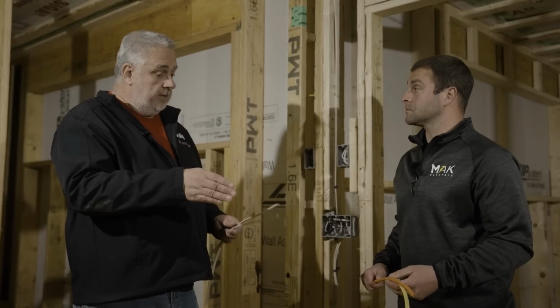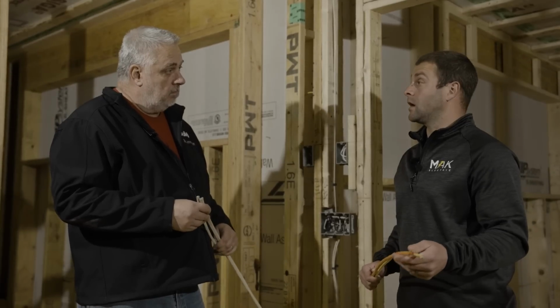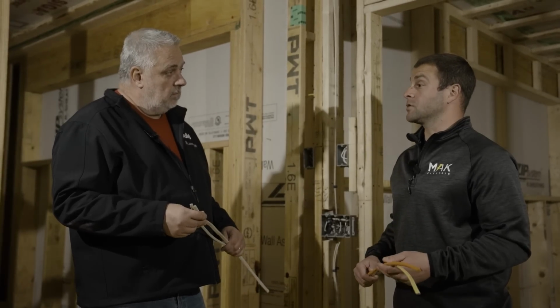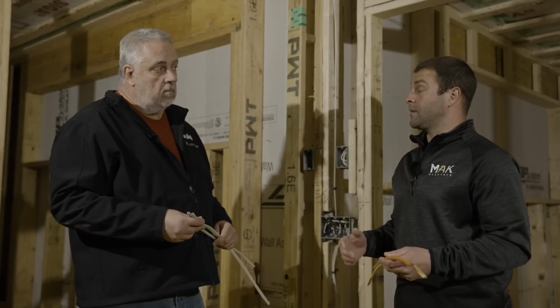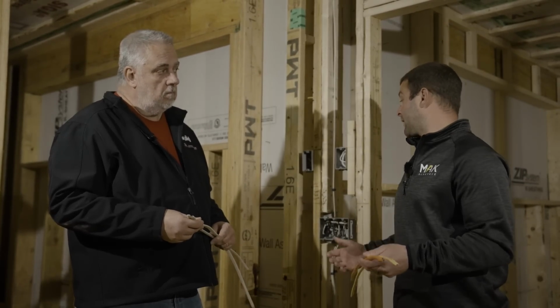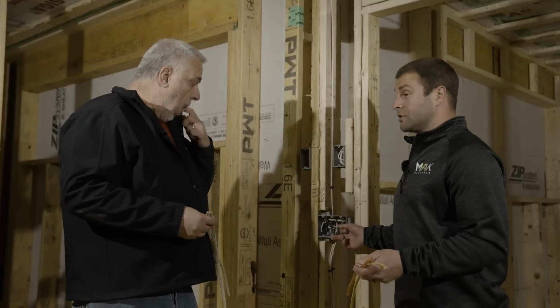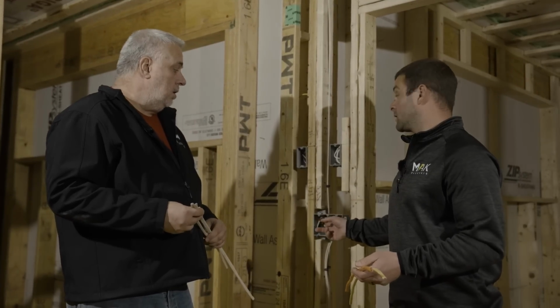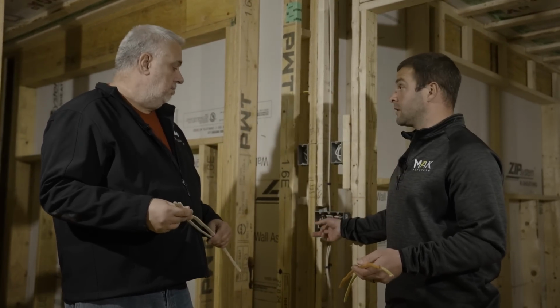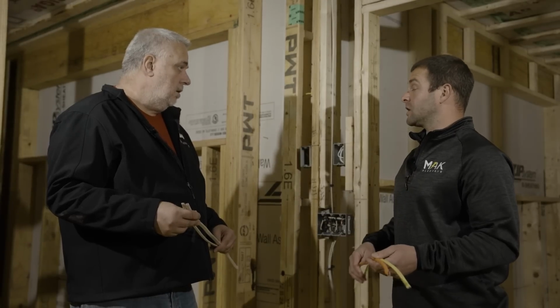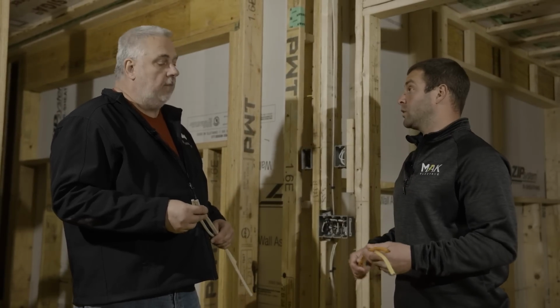The reason for the 12-3 is it has a wire that allows you to add another switch leg, another wire, to turn maybe just a heater on in a fan. So basically, if you're in a bathroom like we are, you'd have one switch that turns a fan on, one switch that turns the heat on the fan on, and then the other turns the light on.